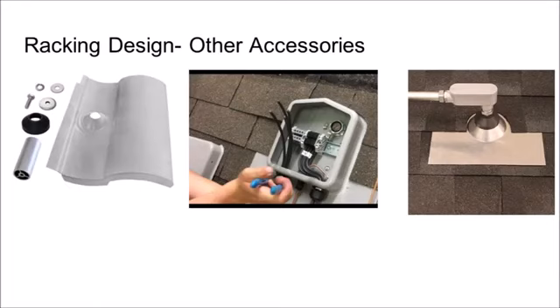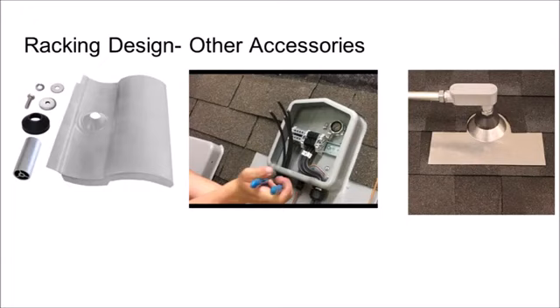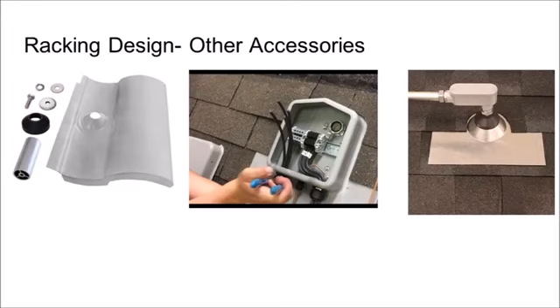There are also inexpensive code-compliant ways to make the roof transition. For example, a flashed pipe boot from the local hardware store can have electrical conduit stubbed up through it for the cable to transition from roof to attic. One caveat with generic off-the-shelf components: there is only about four inches of clearance between the roof deck and the top of the solar panels. Locally-found junction boxes are often six inches deep, making it easy to conflict with the array. When using generic components, I commonly skip the roof box by transitioning cables through conduit via a cable gland, then landing in a box in the attic.